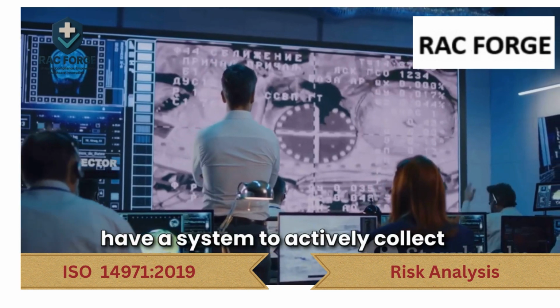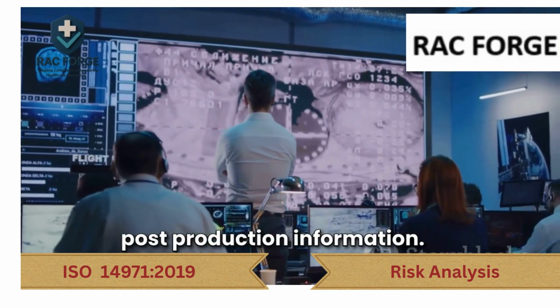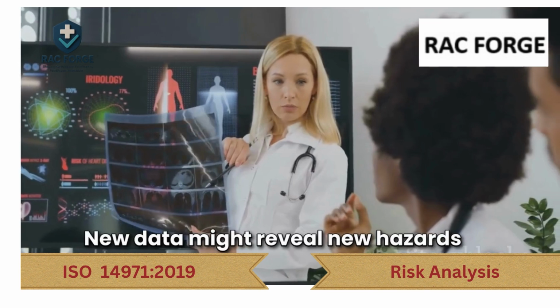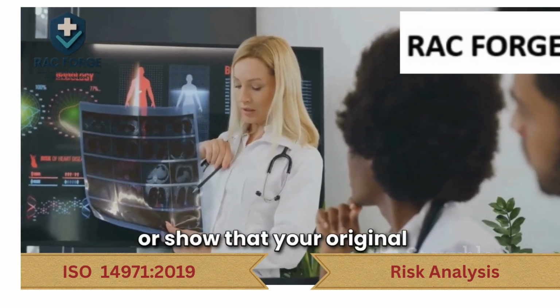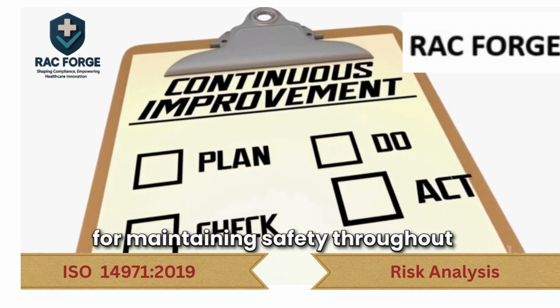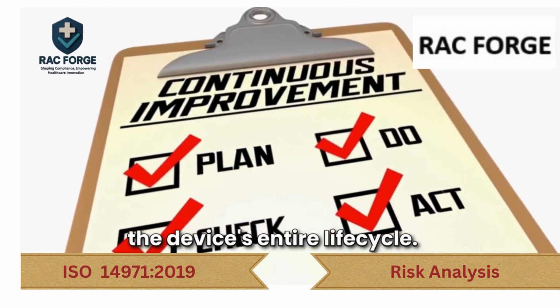You must have a system to actively collect post-production information. New data might reveal new hazards, or show that your original estimates have changed. This feedback loop is essential for maintaining safety throughout the device's entire life cycle.